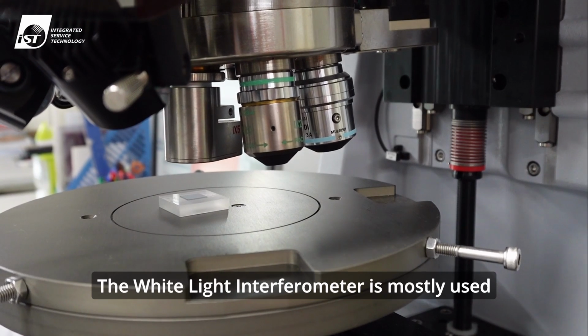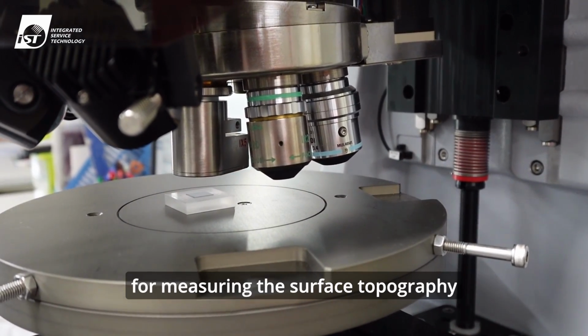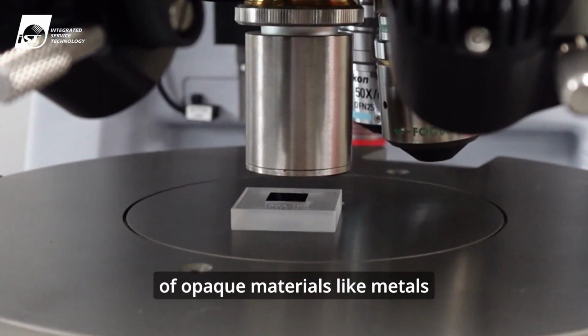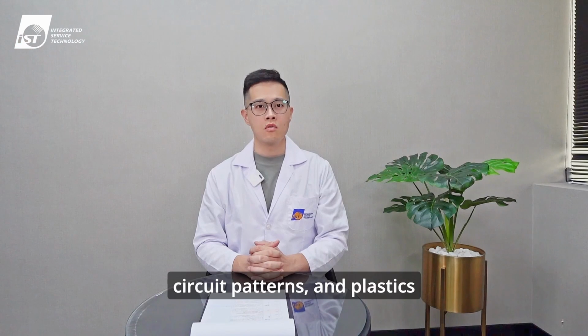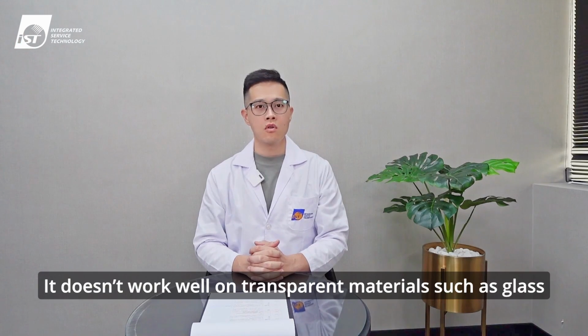The white light interferometer is mostly used for measuring the surface topography of opaque materials like metals, circuit patterns, and plastics. It doesn't work well on transparent materials such as glass.